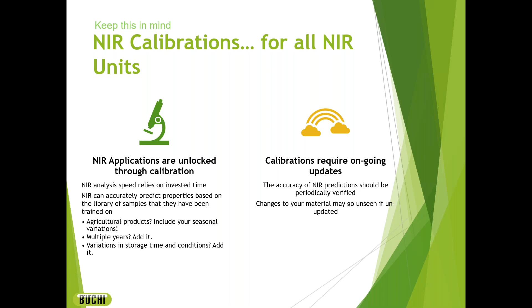So what does a calibration look like? All right, so this is a calibration for starch. The horizontal axis is the measurement of the starch content of the corn flour that's done by the primary method. Let's call that the gold standard. The vertical axis is the NIR prediction. In an ideal case, the calibration curve will be a 45-degree sloped curve, as you see here, with minimal deviation around that curve, which is what we do see in this particular case.